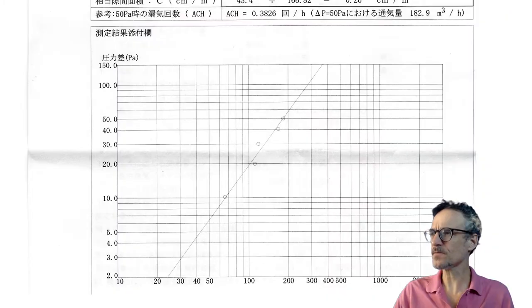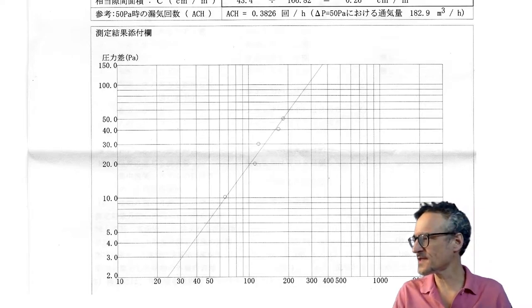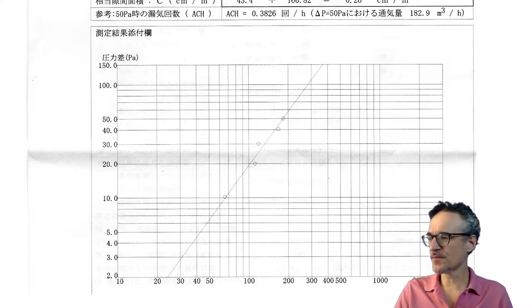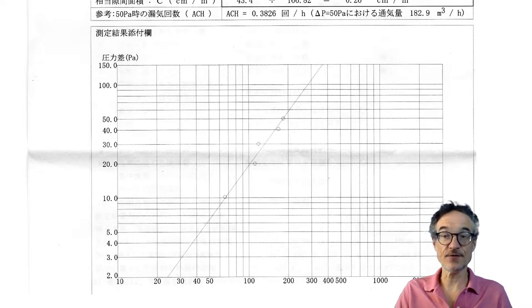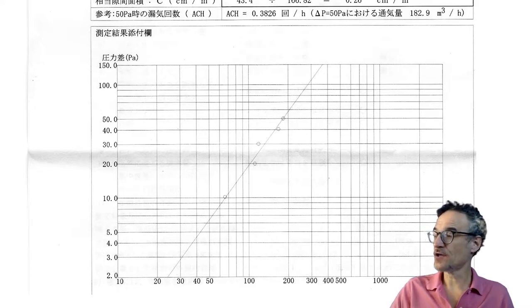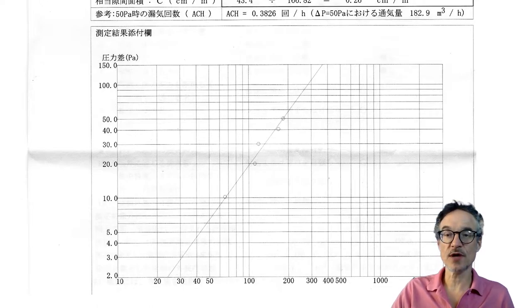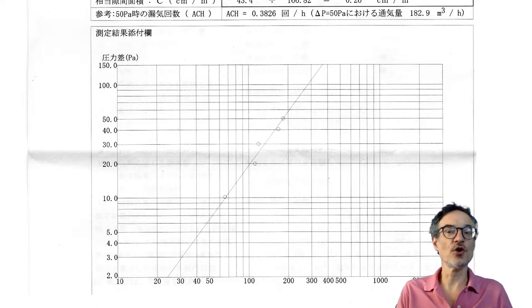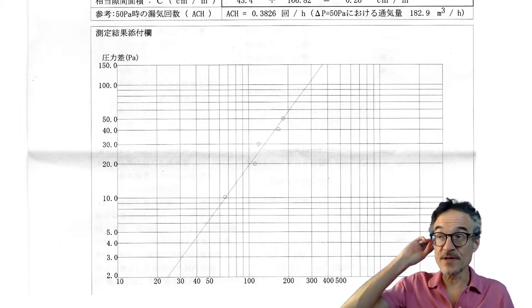So we can measure airtightness, and we do measure it for low energy buildings because airtightness is important. When you measure it you get a graph — a plot of pressure against how much air is leaking through — and from this we can work out how many air changes per hour. You can also calculate back to the C-value from these measurements.